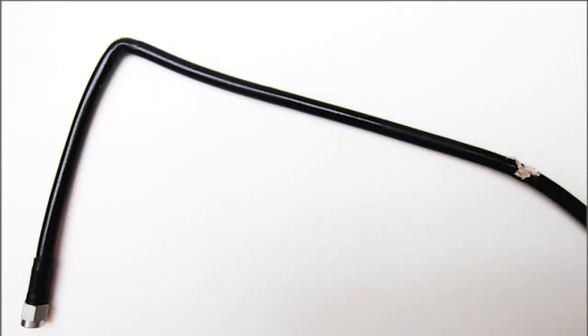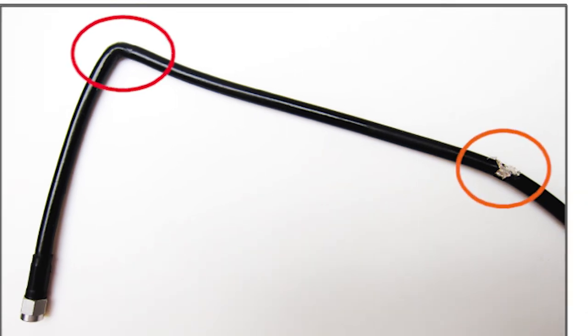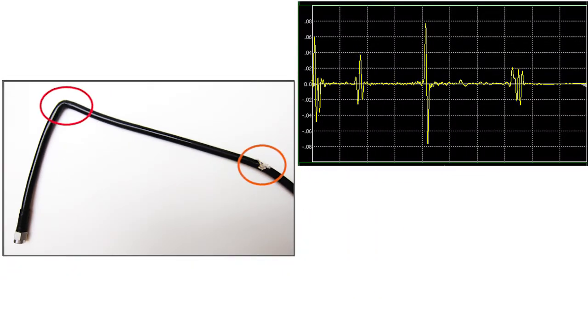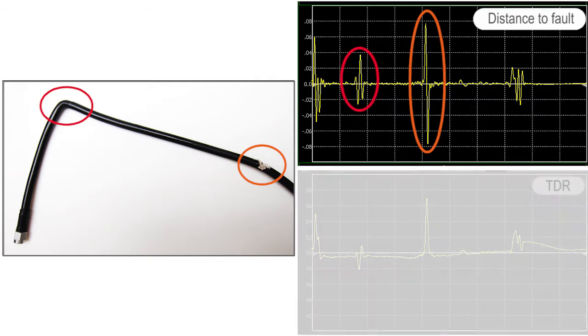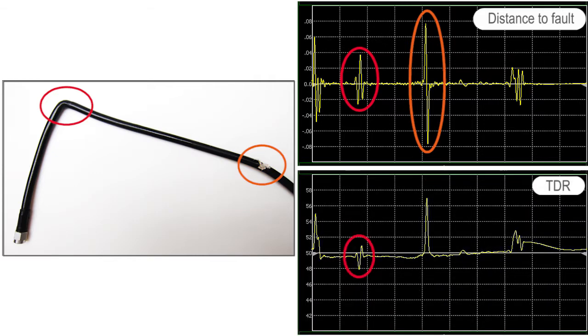In the case shown here, we have a damaged cable with bend radius exceeding specification and a nick in the outer shielding and dielectric. The distance to fault function shows exactly where the faults are and the TDR function shows the bend fault as capacitive and the nick as inductive, helping the technician figure out what the faults are.